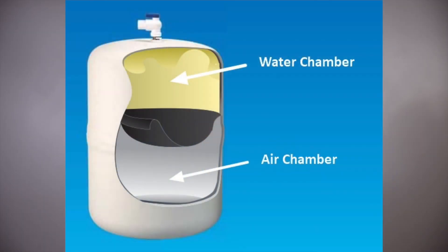The recovery is calculated at 25%. But the reality is, when you hook that storage tank up, those numbers all change. The storage tank, being hydropneumatic, collects the water. Inside the tank there are two chambers: one where the water goes, and one where the air is. The air will compress where water will not. As water enters the storage tank, it compresses down into the air chamber, and as that air chamber compresses, the pressure goes up.